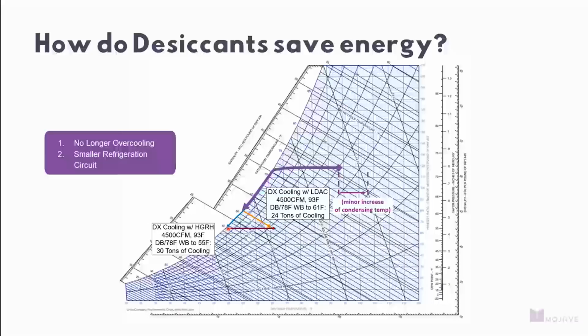With a liquid desiccant system, and specifically Mojave Arc2Dry, you're still using a DX system to do a portion of the work, cooling and partial dehumidification, stopping short of your final discharge dew point with that DX system. So only doing the easier portion of the work with the DX system. The reason it's the easier portion of the work is as you get further down and to the left on this saturation curve, those enthalpy lines get tighter and tighter together. You get diminishing returns for the amount of energy input. And what that translates to is bigger coils, more refrigerant, bigger compressors for each degree colder you push your subcool on a DX system.